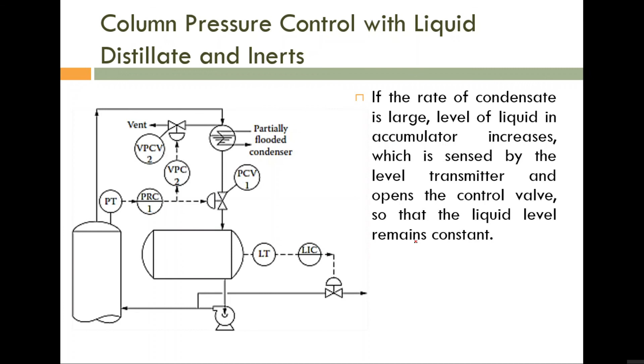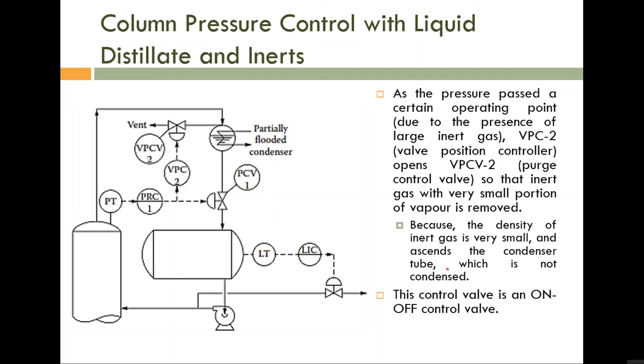Is it okay? So please note, liquid level inside the accumulator must be constant. Otherwise, the vapor pressure will depend upon both the condensation rate and the liquid level inside the accumulator. So in order to avoid that, in order to avoid the multivariable, otherwise we have to implement multivariable control. That is a difficult one. So in order to avoid that, this liquid level is maintained constant. If you are considering this controller, the pressure is depending only on the condensation rate, if you are maintaining liquid level constant. So that is the purpose of this liquid level. Now, here we discussed the second controller. I told you this is an on-off controller.